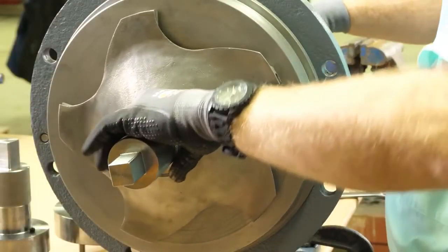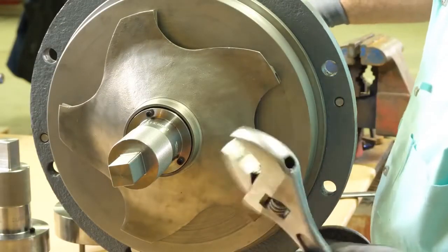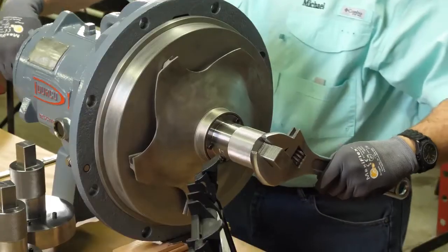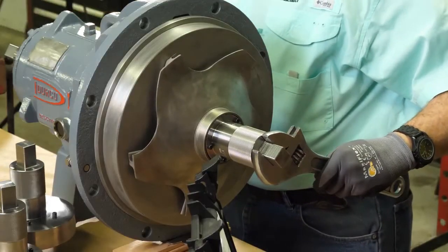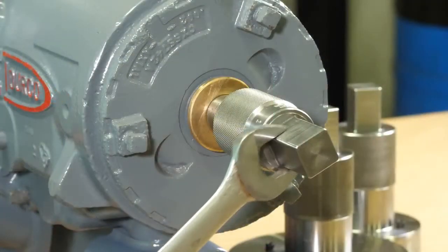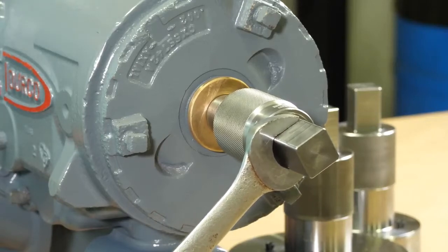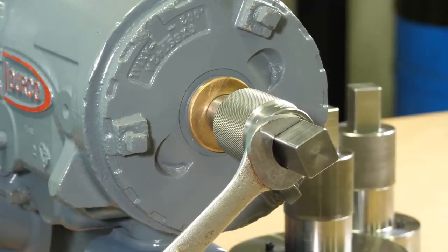Lightly turn the socket to ensure all vanes are engaged. Apply either a one-inch combination wrench or crescent wrench to the squared head of the impeller wrench. While keeping one hand on that wrench, take either a one-inch combination wrench or a crescent wrench and apply it to the squared end of the drive end socket.